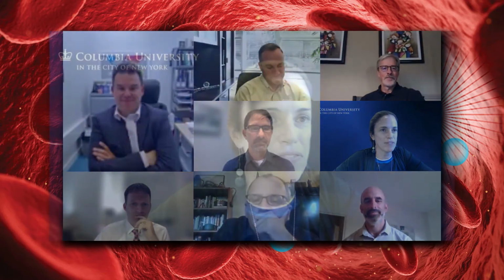I would also learn something from imaging, which is basically the phantoms, right? So when you get a new scanner, you get a new transducer, you have a phantom that's AIUM approved, and basically you check your resolution, your intensity, your contrast, all that's important in imaging. We can have something equivalent, a flow phantom that's also used for Doppler, for example, and then we can run bubbles through it. There's a small infusion pump that runs to the phantom. And I think this is a little bit better than just water, right? Because we know things break in vivo and also ex vivo.